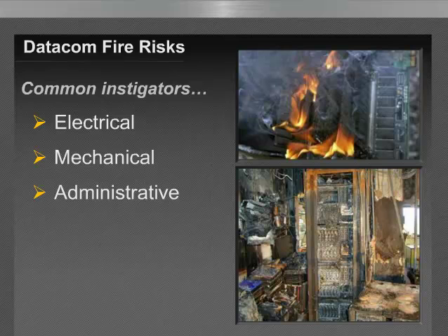Also mechanical systems, such as HVAC systems malfunctioning. HVAC systems also aid the circulation of smoke and gases to other compartments, and this ultimately can lead to damage of electronic devices and other compartments. We also look at the risks of generators, fuel lines, and exhaust lines. And let's not exclude administrative factors, such as bad housekeeping and storage practices. And densely packed arrangements of equipment and fuel sources will encourage the spread of fire and smoke contamination within these types of environments.